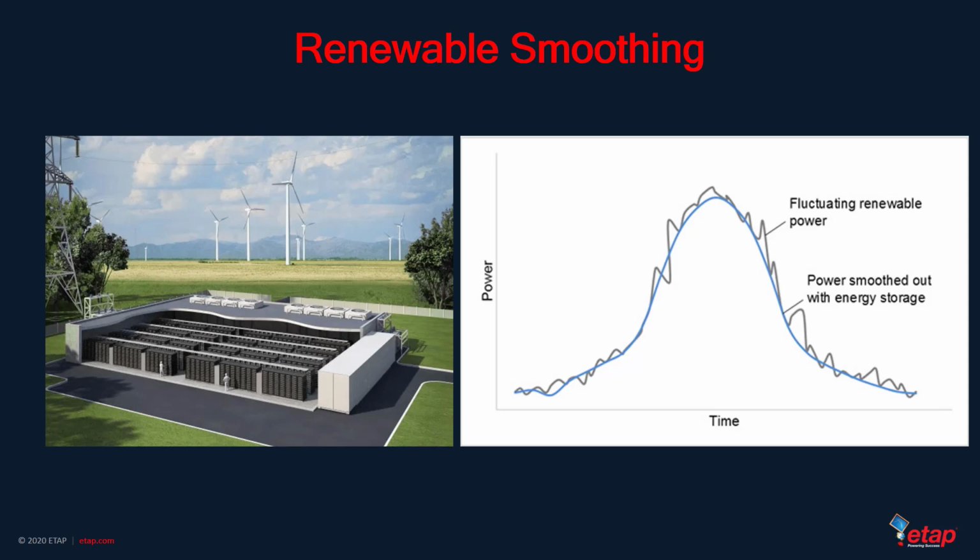Now, besides smoothing in big solar plants and wind farms, the grid operator asks energy providers to provide power with minimum difference from one time to another. We add this constraint on top of the smoothing problem. Then we determine a minimum possible size of energy storage system so that the smooth output power is maintained during the day ahead forecast period.